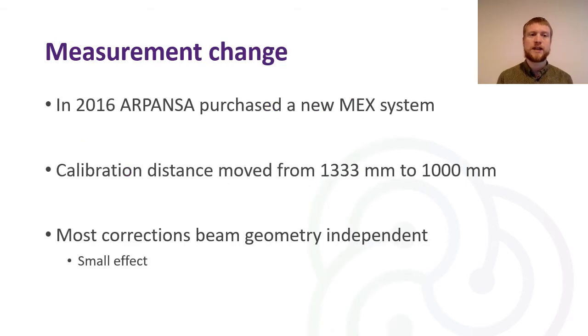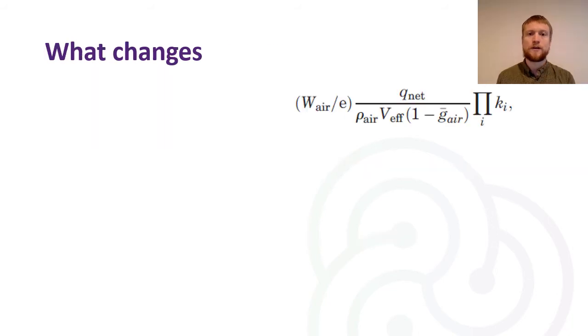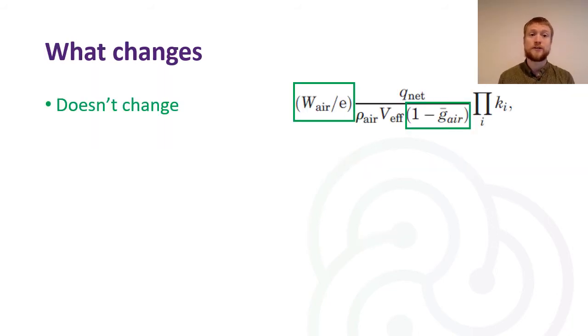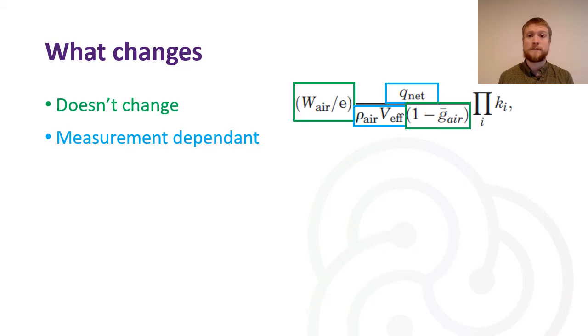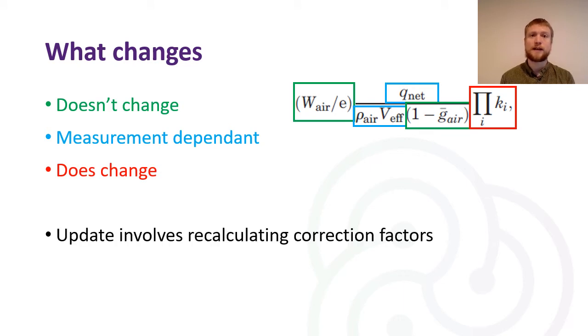Also necessitating a change is that in 2016, ARPANSA purchased a new medium energy X-ray system. So the calibration distance moved from 1.3 meters to 1 meter. This is expected to be small as most of the corrections are beam geometry independent, so we expect this to be a small effect. So if we have a look at what does change, we know that the W air value and the G of air value don't change. So the other values are measurement and free air chamber dependent, so it is then the correction factors that do change. So this update involves recalculating all of those correction factors, taking into account ICRU 90.